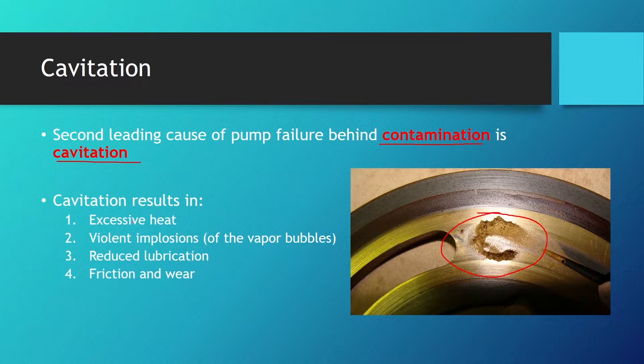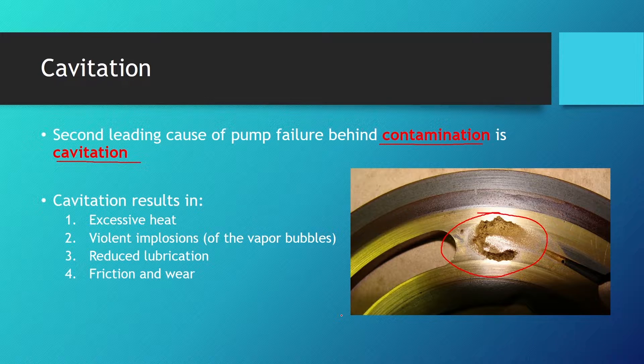Cavitation results in excessive heat, violent implosions of the vapor bubbles, reduced lubrication because the oil loses its viscosity and lubrication characteristics, and friction and wear. Cavitation is a condition that can also potentially damage or compromise your hydraulic system. For this reason, understanding cavitation, its symptoms, and methods of prevention are critical to the efficiency and overall health of not just your hydraulic pump but your entire hydraulic system.